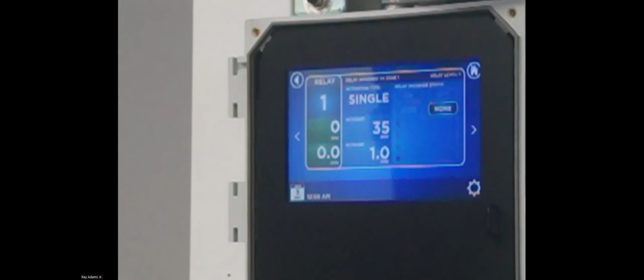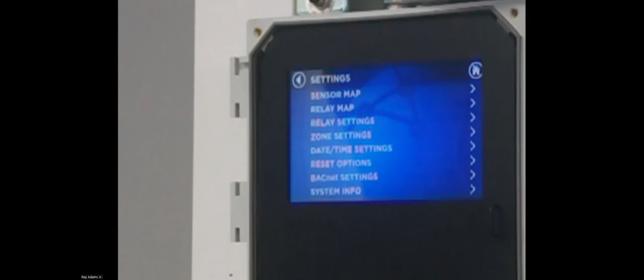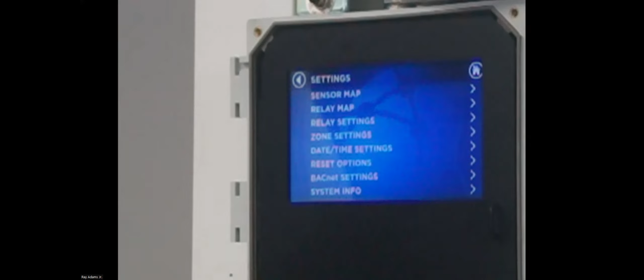So as this is sitting in a parking garage or in a facility, nobody has access to come up here and do any of that. However, when you go into your settings here, it's going to ask you for a passcode that allows you to go in and make some of the accommodations that you may want to do in the field. Again, we send it out factory programmed, so that's generally not happening in the field, but there are times where somebody wants to change what the activation level is, maybe add a sensor or two as things go on within a facility. And one of the things that we get incredibly good feedback on from contractors and those in the field is just the simplicity of being able to operate a touchscreen.